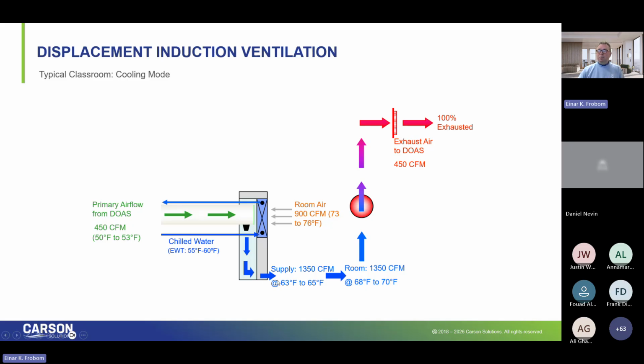The supply air comes out of the diffuser, comes in contact with the student to create that displacement operation. So this is 2 distinct technologies in one device. It's displacement that is occurring out in the space, and the induction process is what's occurring at the terminal unit. So displacement, induction, ventilation.